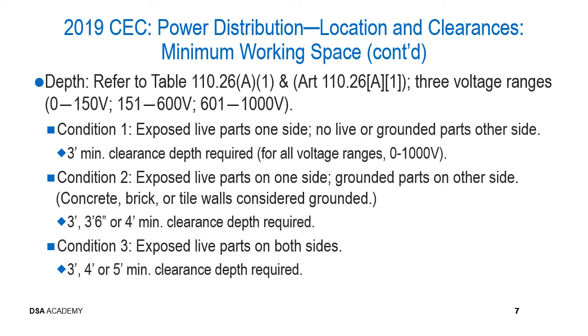Now condition number 2 is defined as an area where there are exposed live parts on one side of the room and grounded parts on the other side. Grounded parts meaning concrete, brick, or tile walls, for instance. Those are considered grounded. In these conditions, condition number 2, either 3 feet depth, 3 foot 6 inches in depth, or 4 foot minimum depth clearance is required. Condition 3 is a condition where you have exposed live parts on both sides of the room. And again, dependent on some other parameters that we'll discuss in the next slide, either 3 feet minimum depth, 4 feet minimum depth, or 5 feet minimum clearance depth will be required.